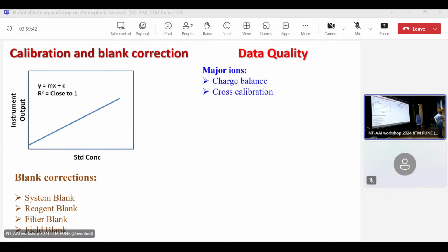I measured chloride. Then I took some sodium chloride and made a standard from that also. Now whatever calibration I made using this commercially available standard, I run this lab-based standard on that. So chloride should come as the concentration I am putting in. That will tell that whatever you are making in the lab is correct.